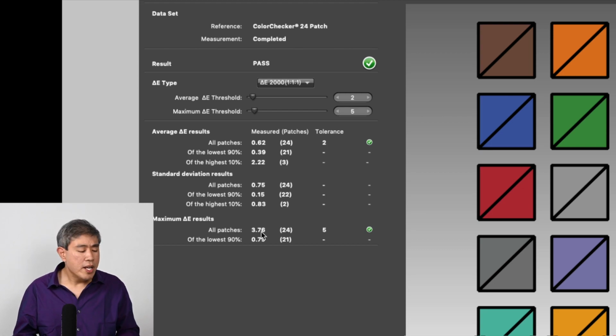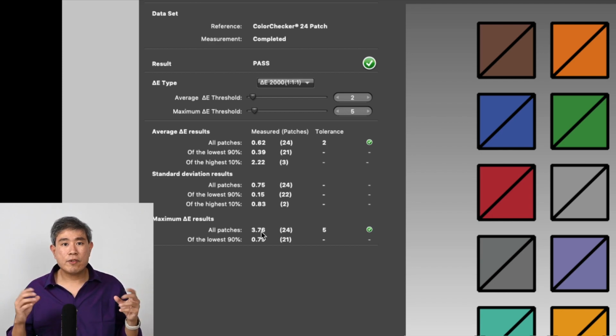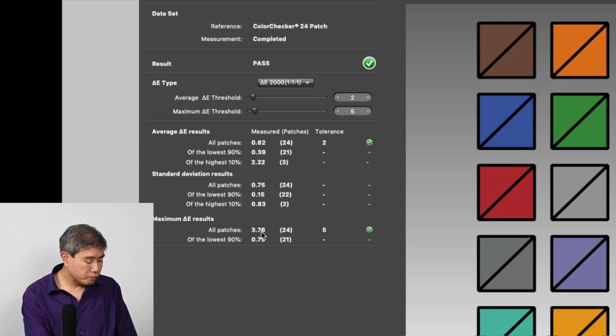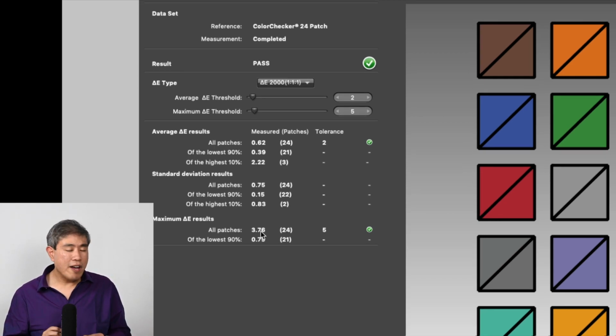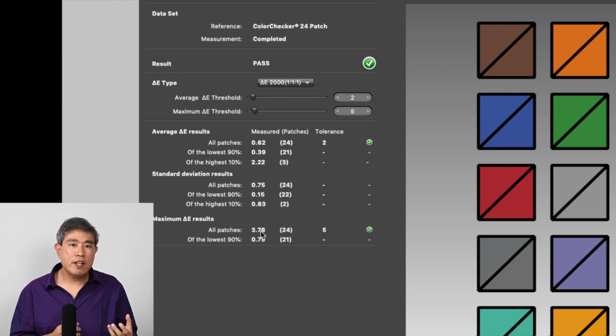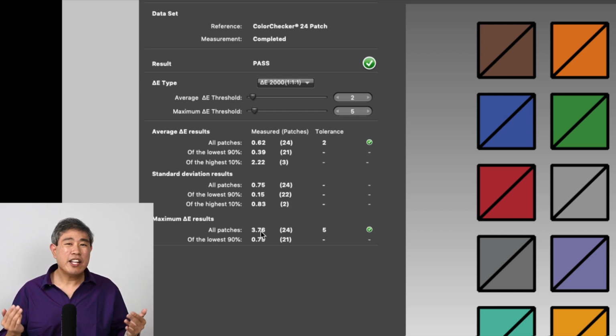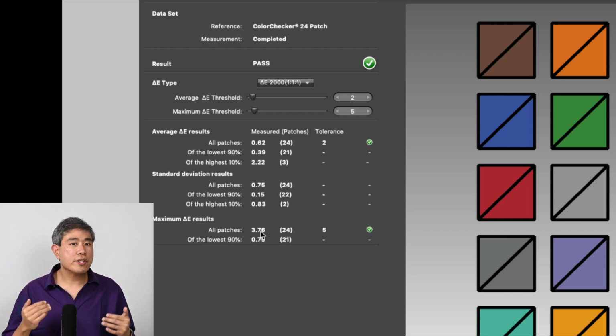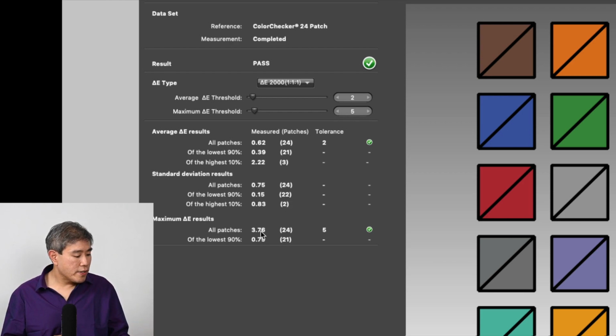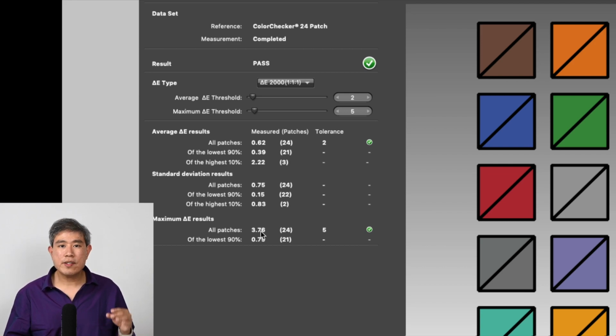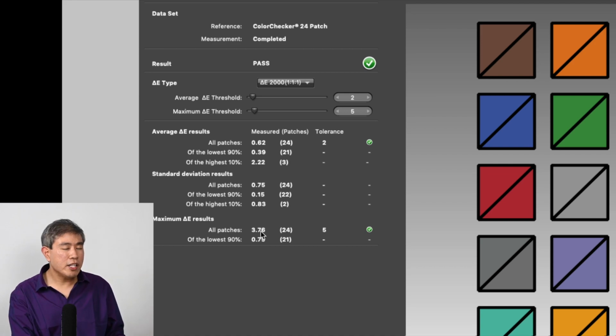So what is delta E anyway? Delta E, what it comes down to is the variation between the color that is measured versus the color of the reference, for all those actual color patches. And essentially what it is that there's an average delta E. The average tells us between all the patches that is measuring, how off are these colors displaying right now. When you can get the delta E value, anything below 2 is considered excellent. Anything below 1, in 0 point something, is always going to be better. In this case, our maximum delta E value, 3.76, is a little high. Now, just to give you a frame of reference, a display is considered acceptable with a delta E value of anything below a 5. So technically we are okay here.